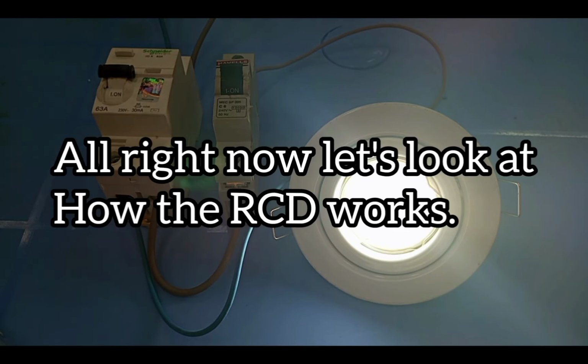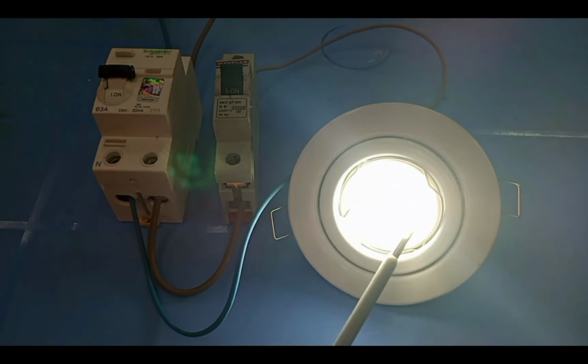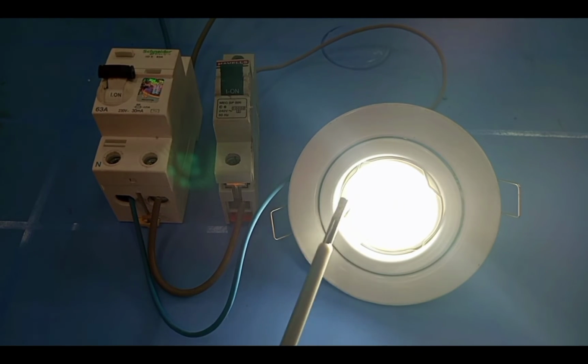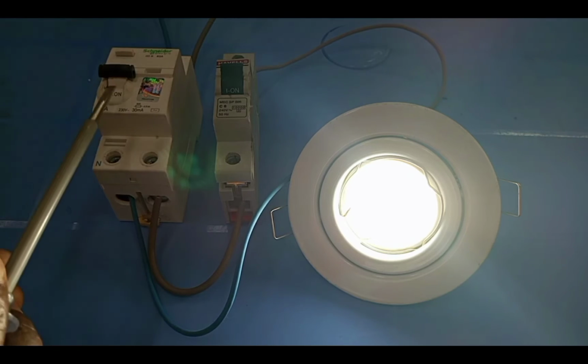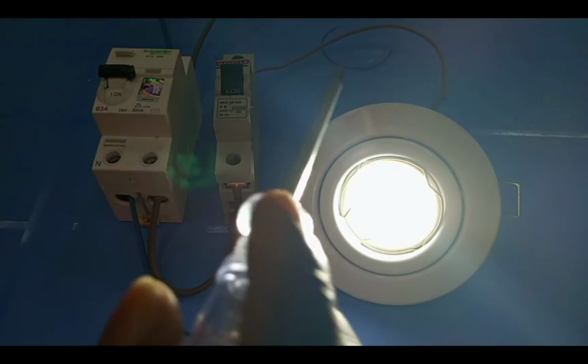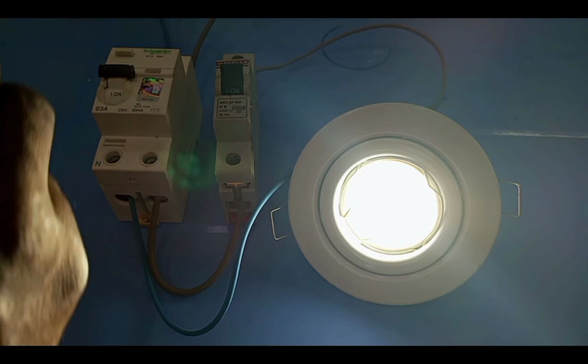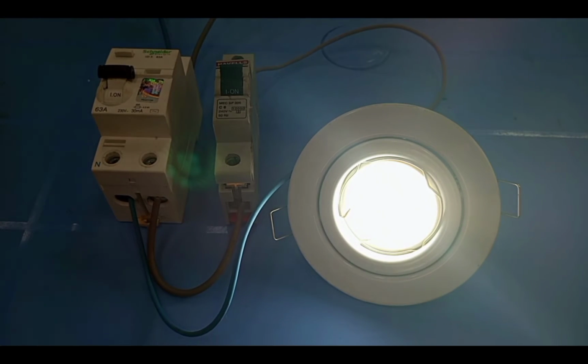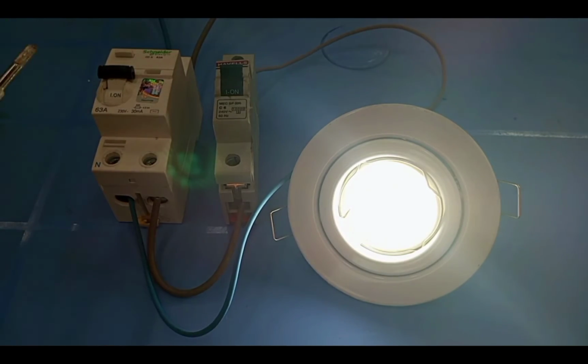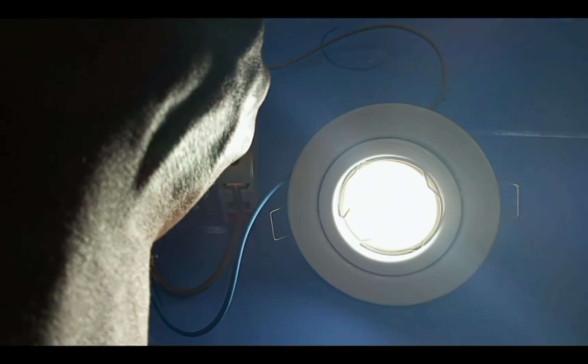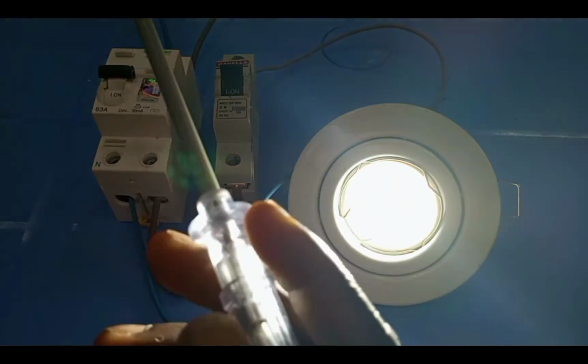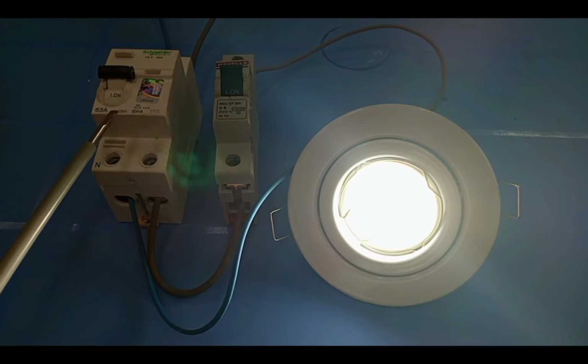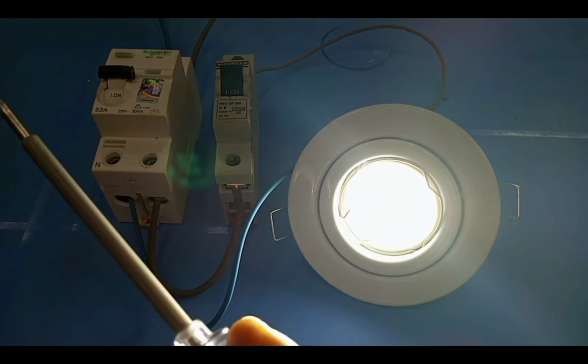All right, so now let's look at how the RCD works. This load is taking an amount of current, let's say 0.02 amps. What this RCD is doing is that it makes sure that 0.02 amps will flow through the live to the lamp and 0.02 amps will flow back through the neutral. The moment it senses an imbalance in the current that is flowing through the circuit, it has to go off. An imbalance is when the current flowing through the live becomes more than the current flowing back through the neutral. This can happen when there is a leakage in the circuit.